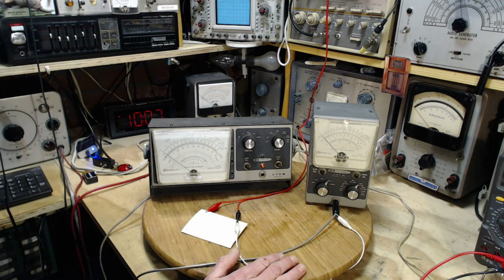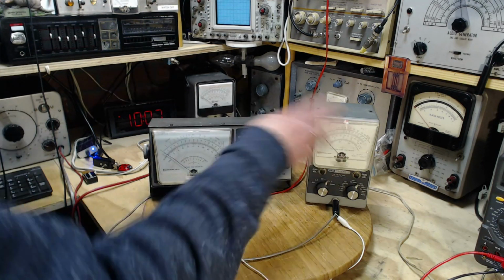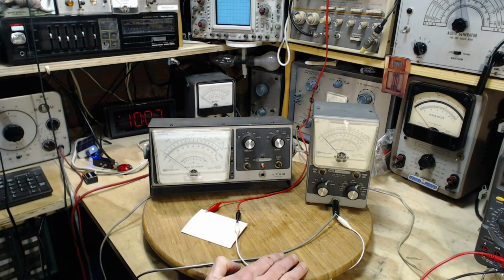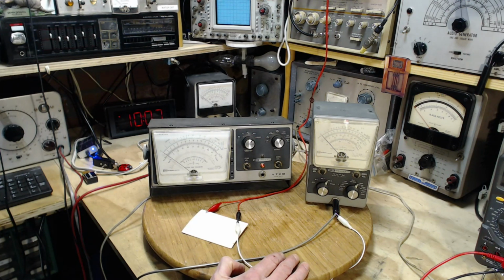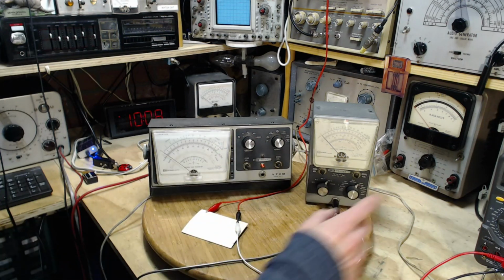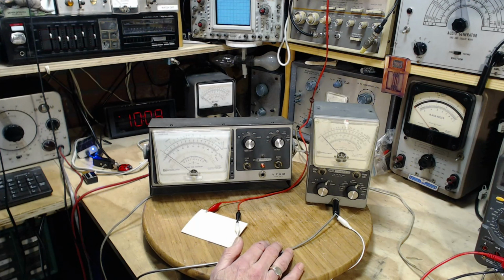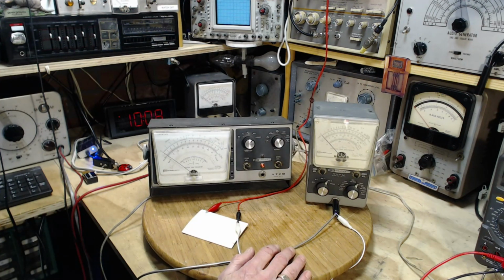Ultimately, I'm pretty sure now what I'm going to do in my shop once I finish restoring this stuff is run a common bus between them to eliminate this case voltage under all circumstances. And if by some chance, with that negative or ground bus running through, I should accidentally energize the bus, then with any luck my circuit breaker will pop open. I'll be safe. Anyway, that's my thinking on that.